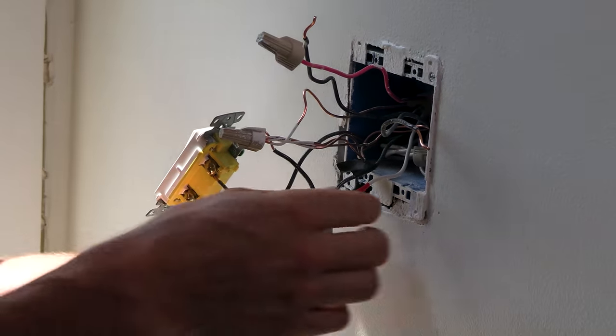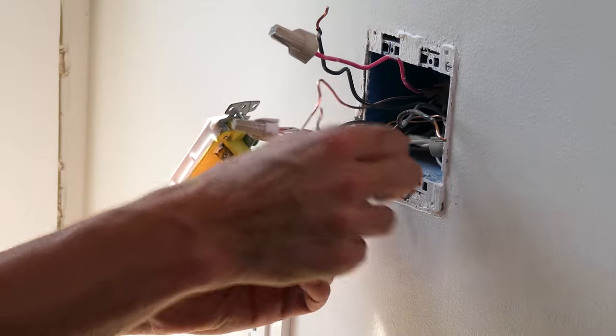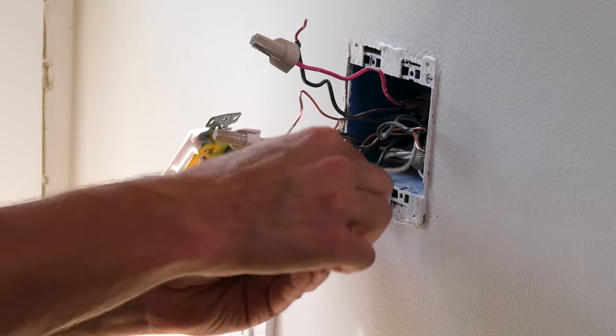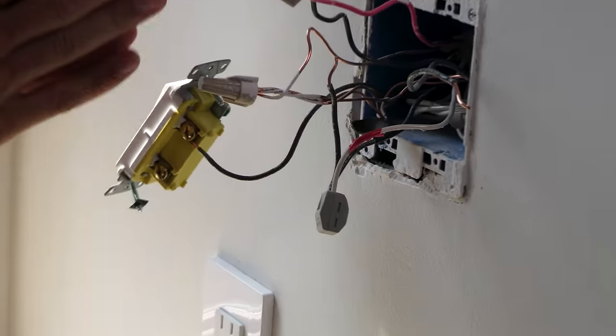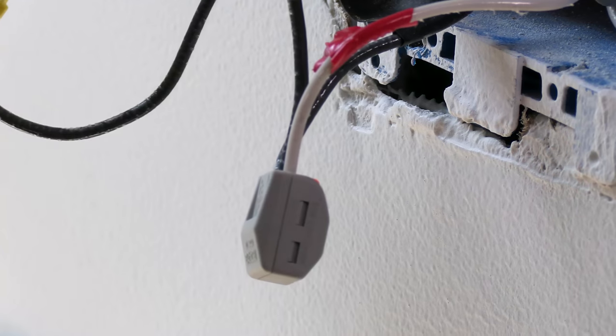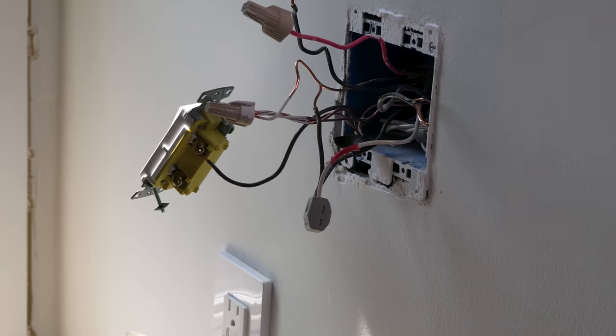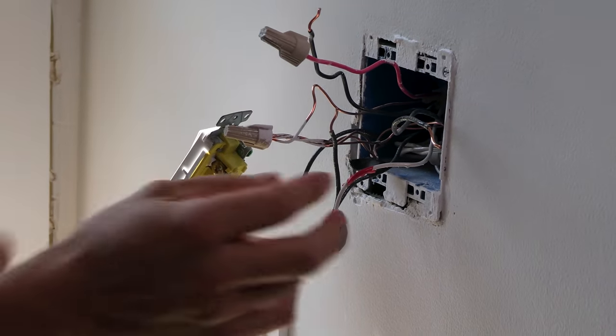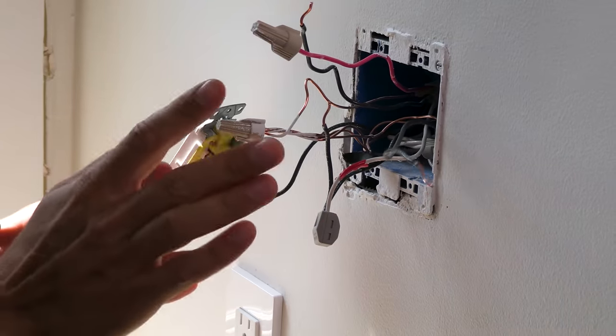And in this case, because I have a dead-end three-way, my white that has been relabeled has now become a hot conductor. So, it's taking places. My hot comes into the box, connects to my white conductor, which jumps to the other end of my three-way, and then my travelers connect there, come back to this box, and then my common is my switch leg. It's going to make more sense here in a minute.